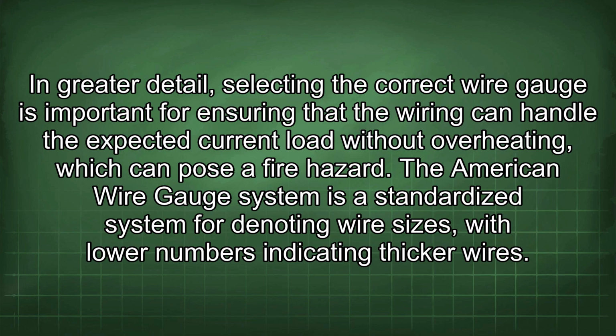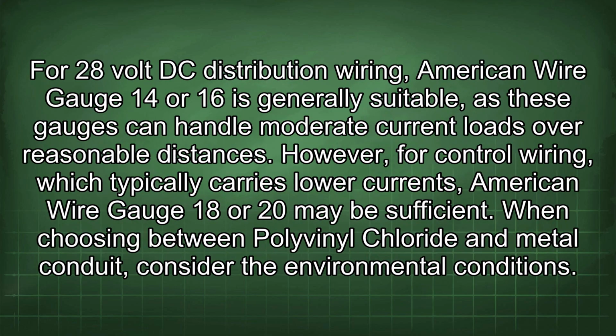In greater detail, selecting the correct wire gauge is important for ensuring that the wiring can handle the expected current load without overheating, which can pose a fire hazard. The American wire gauge system is a standardized system for denoting wire sizes, with lower numbers indicating thicker wires. For 28-volt DC distribution wiring, American wire gauge 14 or 16 is generally suitable, as these gauges can handle moderate current loads over reasonable distances. However, for control wiring, which typically carries lower currents, American wire gauge 18 or 20 may be sufficient.